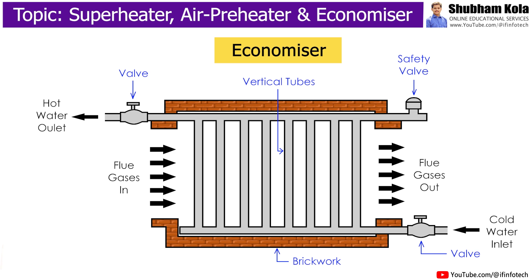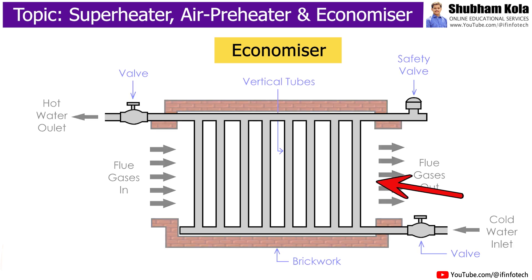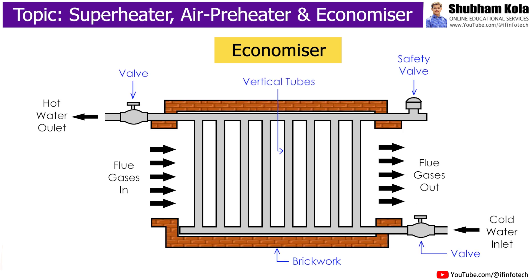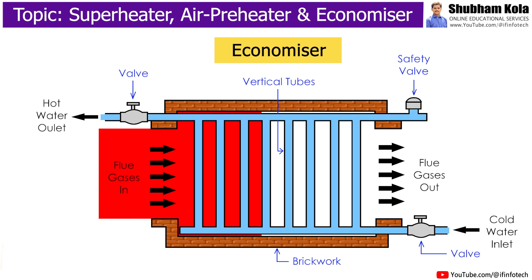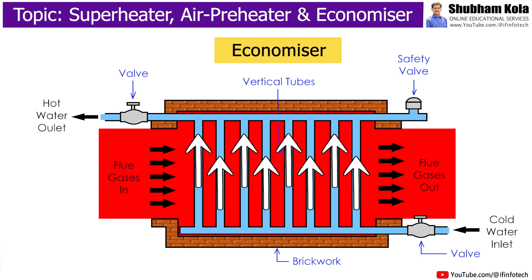The economizer is placed before the air preheater. It consists of a series of vertical tubes provided with a safety valve. The feed water is pumped to the bottom header and is carried up to the top header through a number of vertical tubes. The hot flue gases are allowed to pass over the external surface of the tubes, heating the feed water which flows upward. This heated water is then supplied to the boiler.